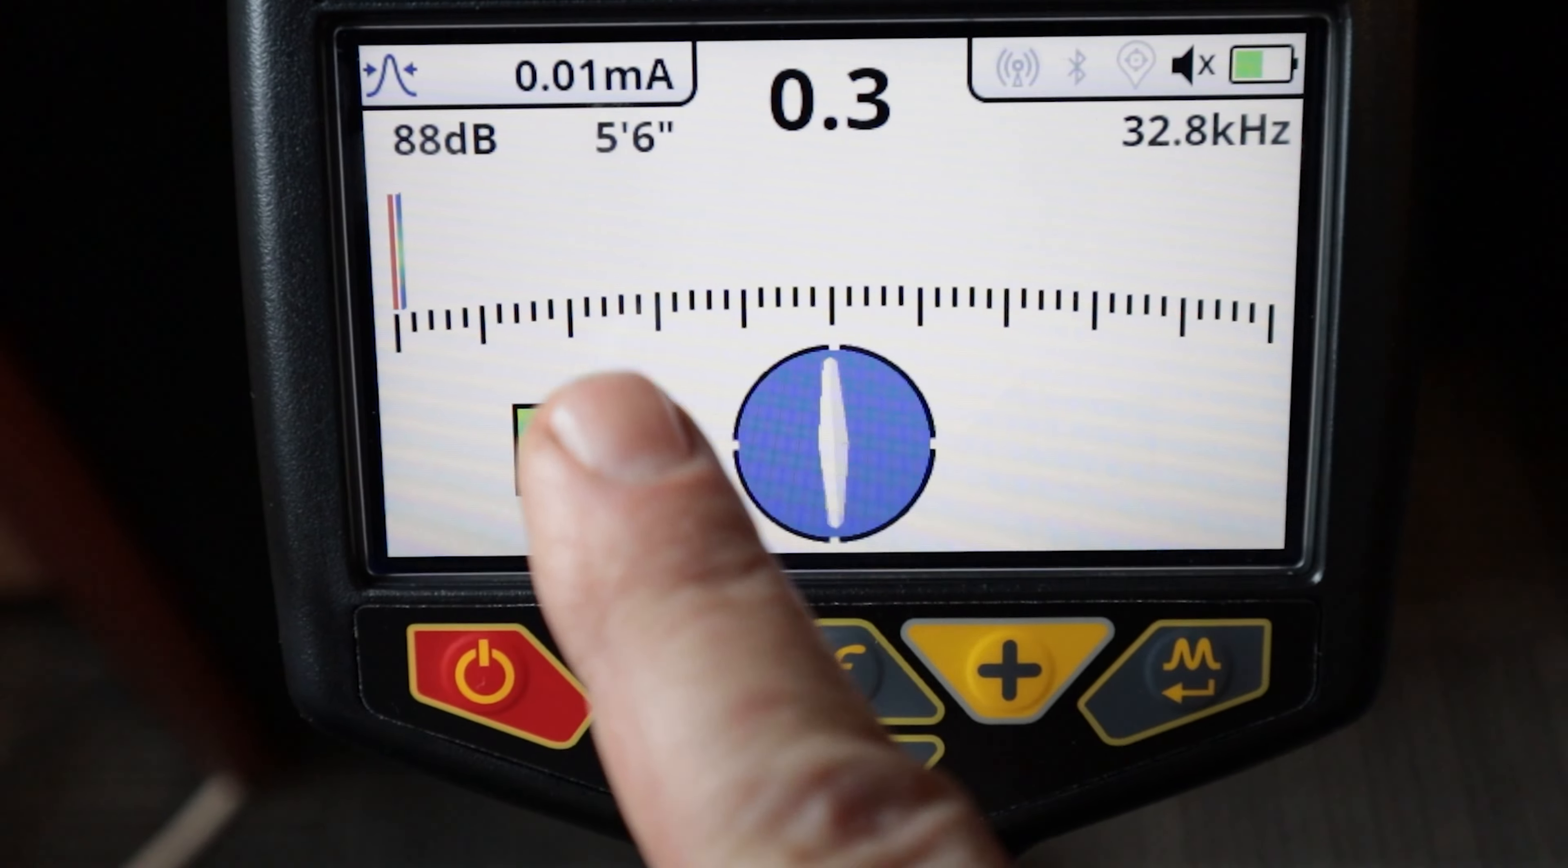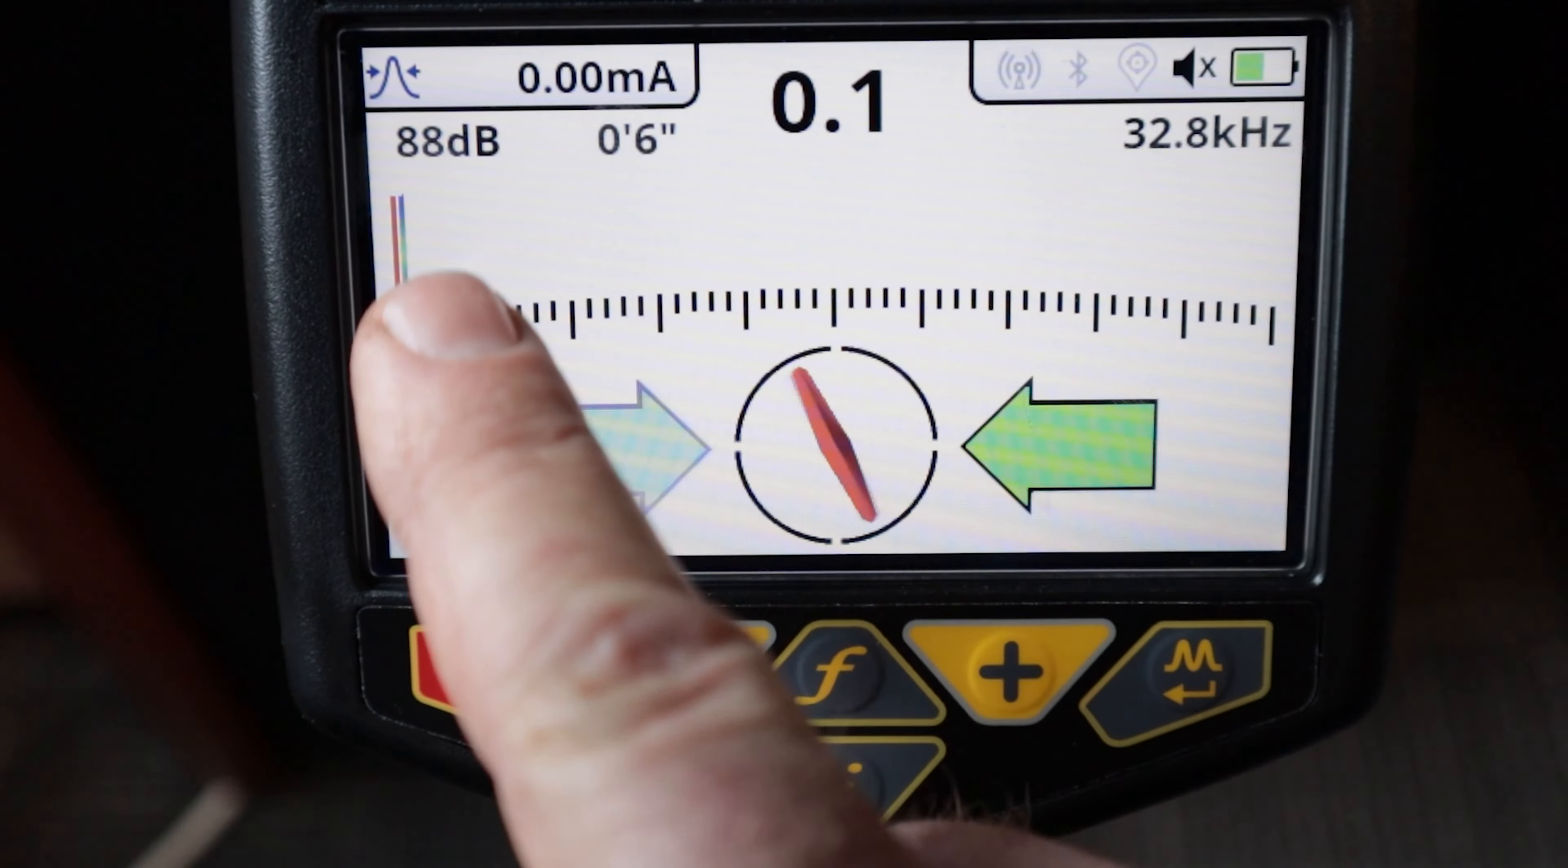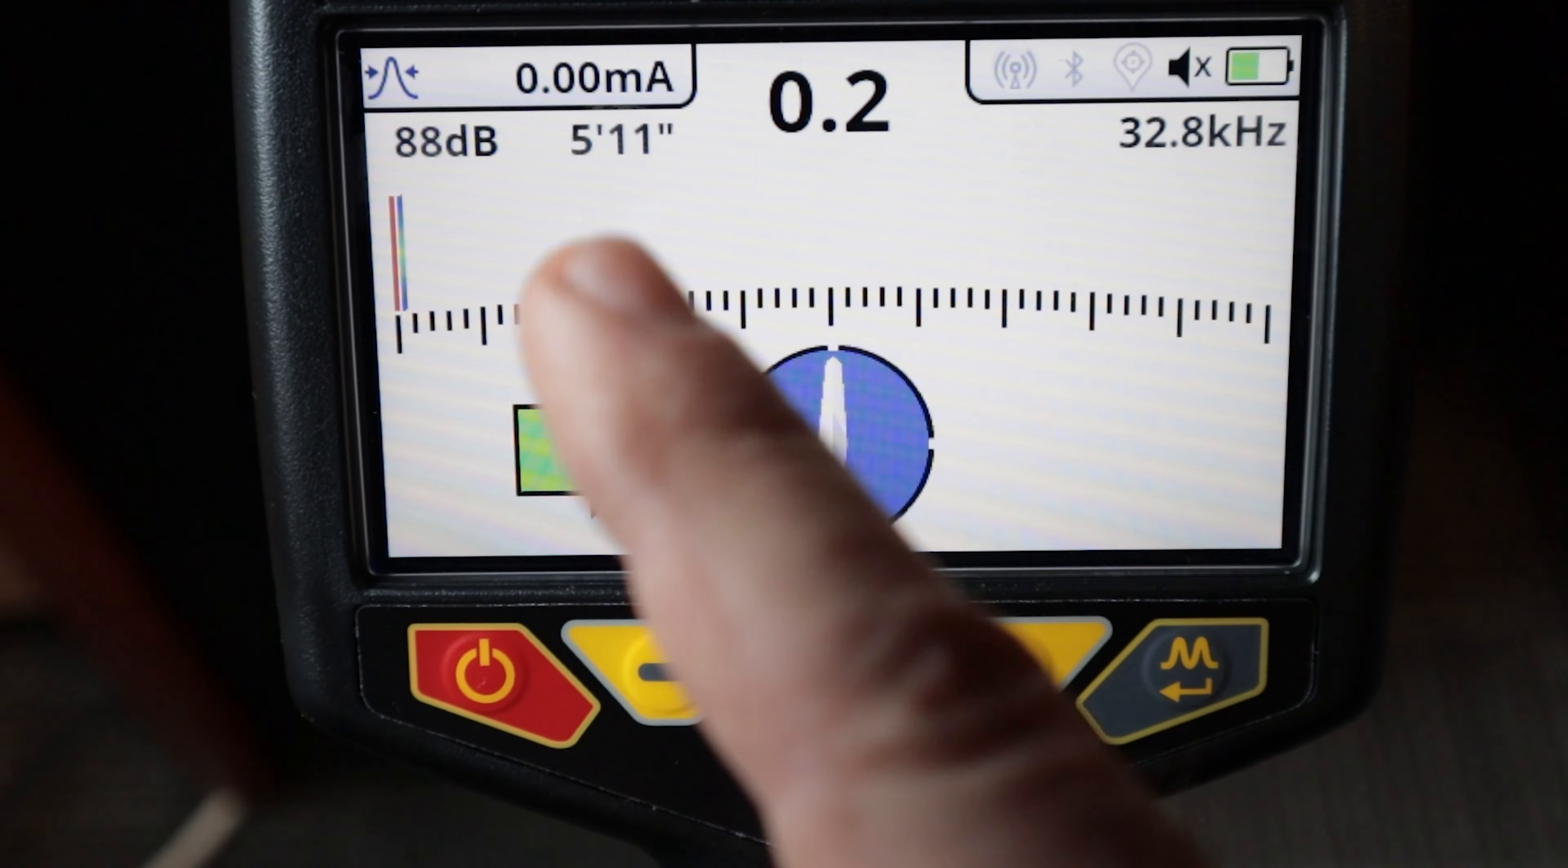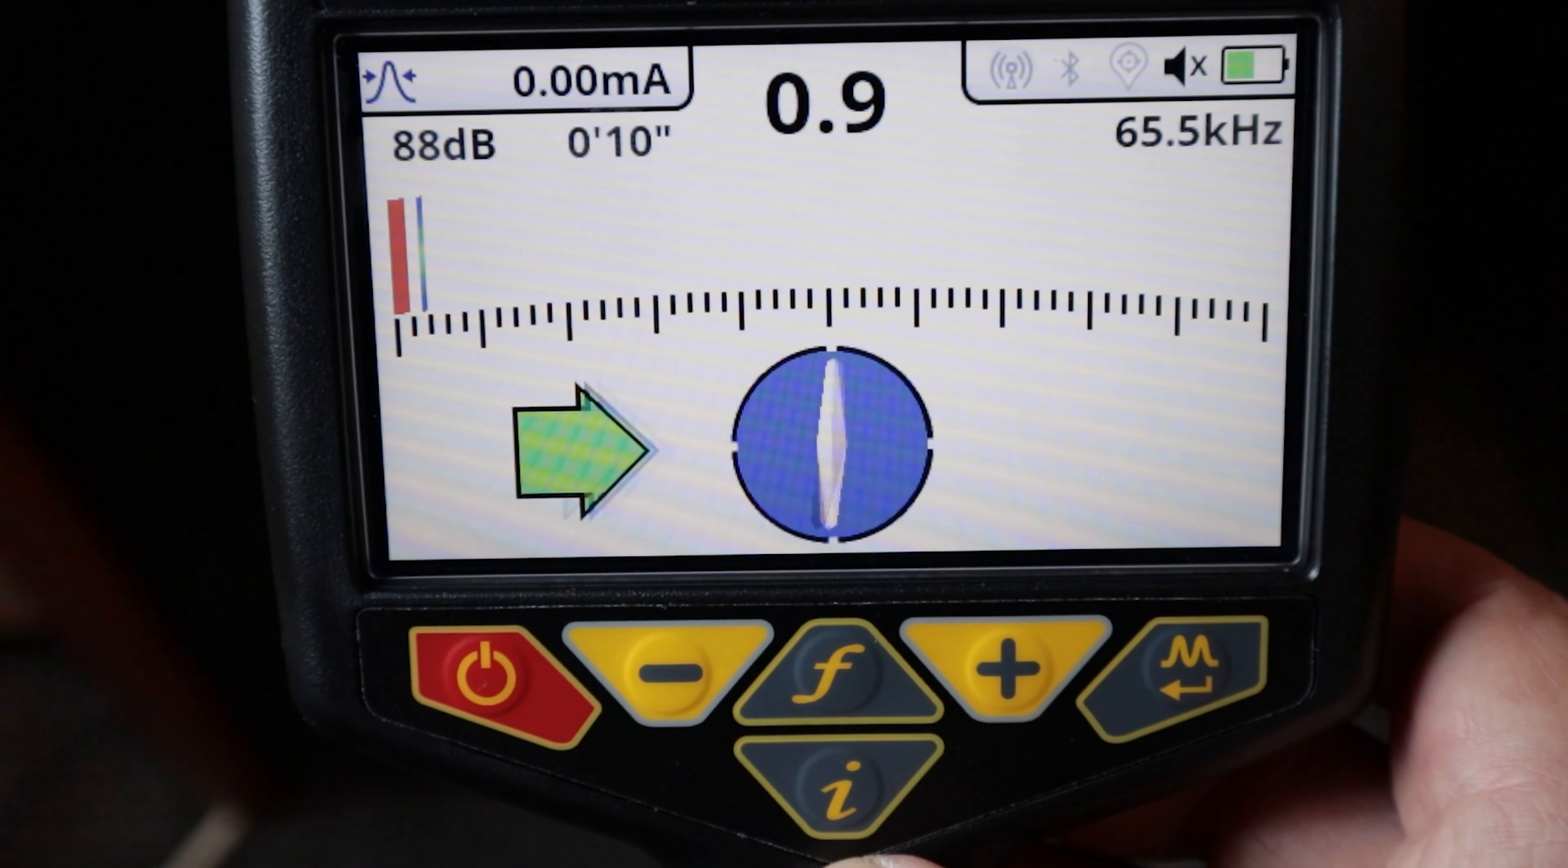Up here is my decibels and that basically is how sensitive I have my coil set to look for the utility that I'm actually trying to find. I don't increase or decrease the actual signal that's being put out, that is referenced by my milliamps. This is just how sensitive I have the coils. An example is if I had something that was quite deep, say six feet deep in the ground, I would need to potentially turn my sensitivity up versus if it was only two feet deep. Next to that is our depth, this is a constant changing depth. Over on the right-hand side we have our frequency.